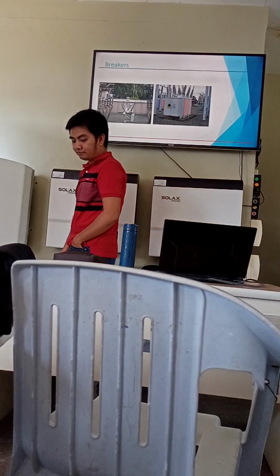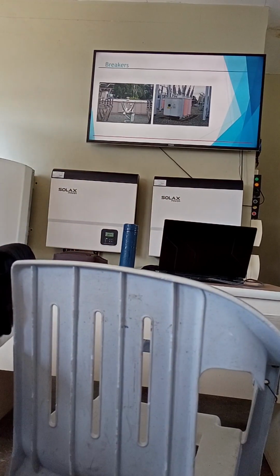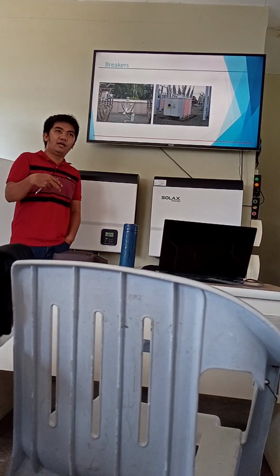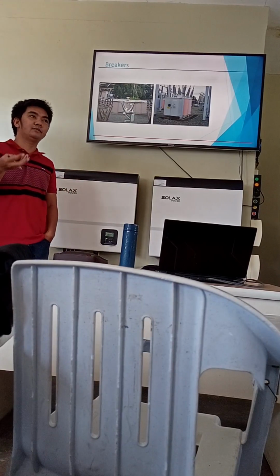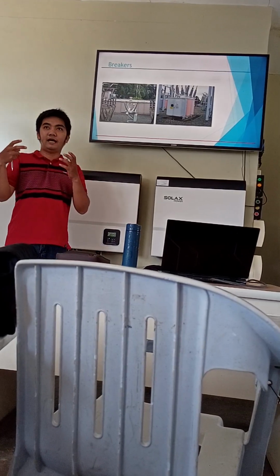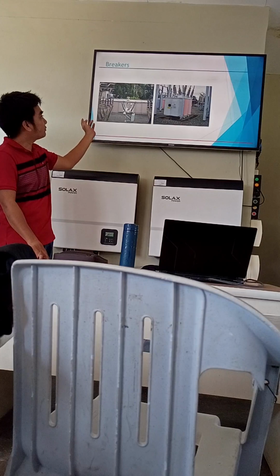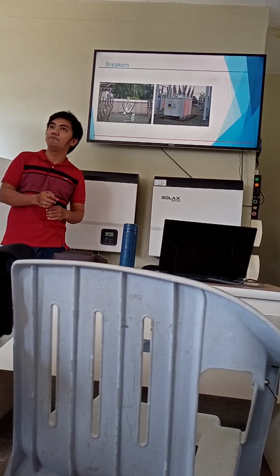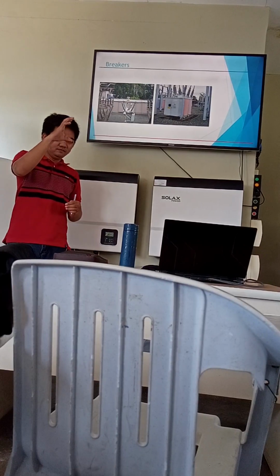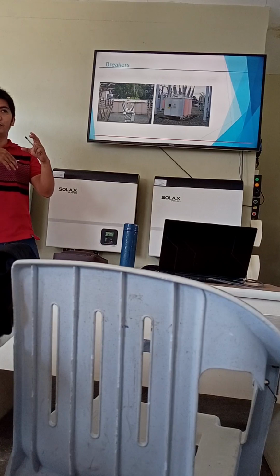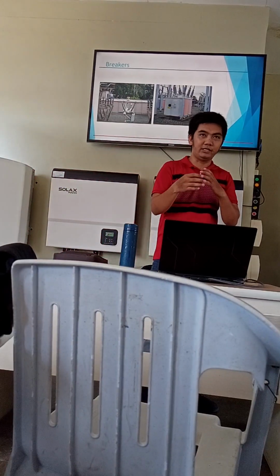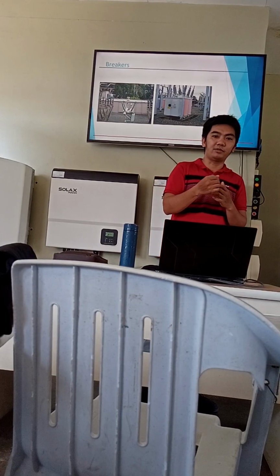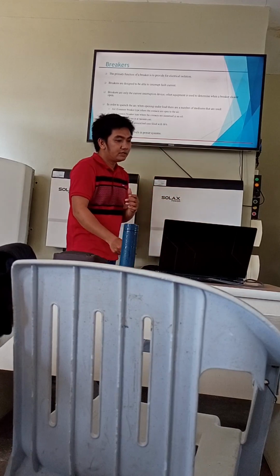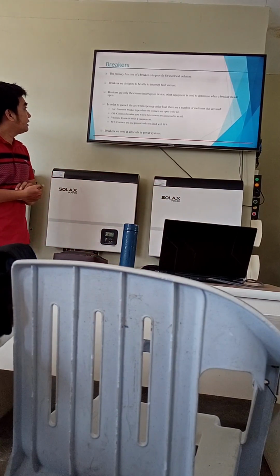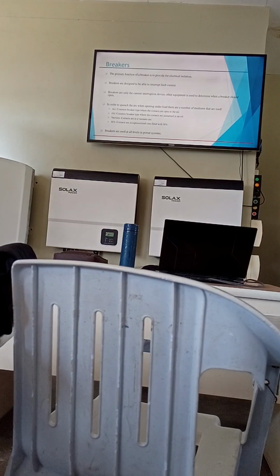Another important component in the distribution system is the circuit breakers. Their purpose is to isolate faults or disturbances and protect assets like the power transformer. The basic construction of a substation has the power transformer with an incoming or outgoing circuit breaker, to isolate faults from entering the power transformer.